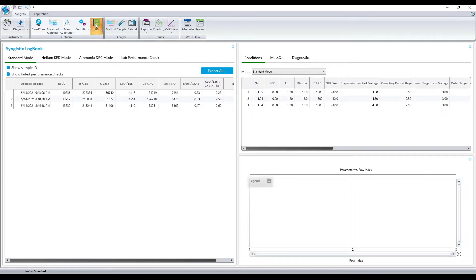The Syngistix LogBook stores the results of the optimization together with all the relevant instrument parameters used in each optimization. This creates a continuous performance history of the instrument which you can use to track instrument performance trends over time and to potentially troubleshoot any problems. To chart any parameter, just click on the column header.